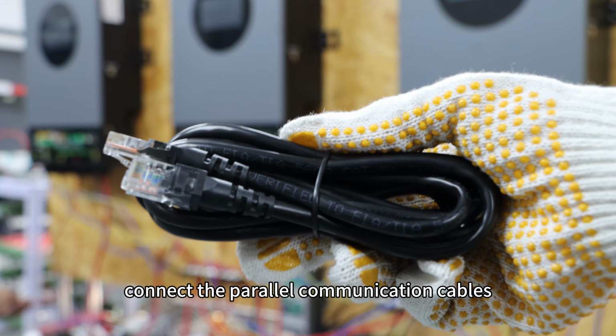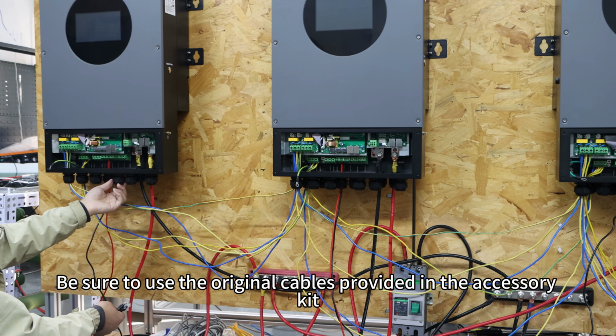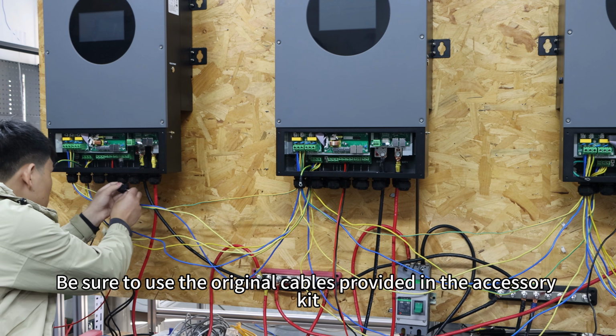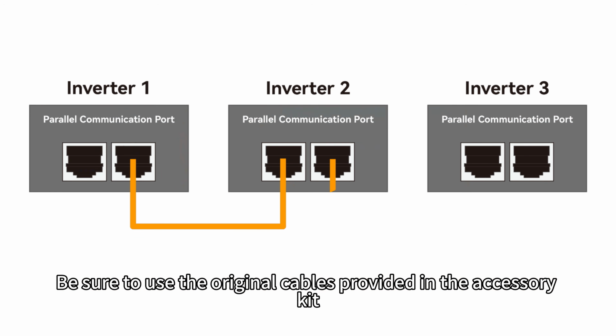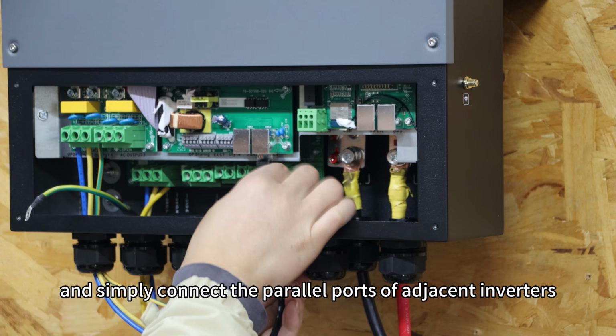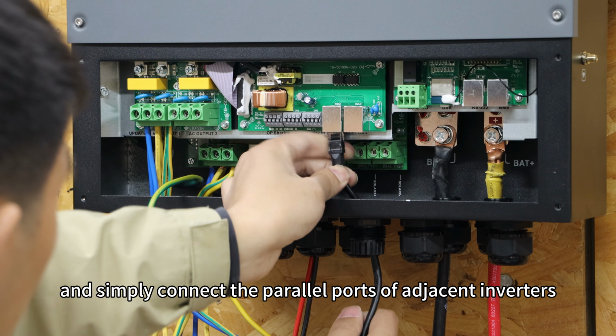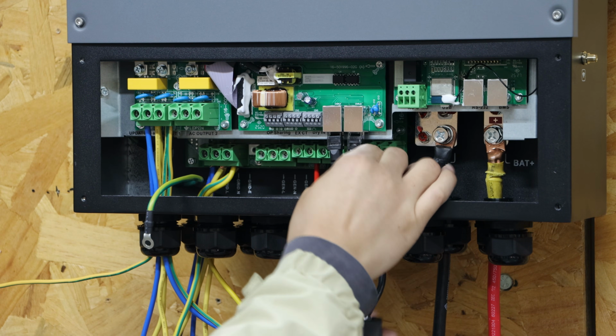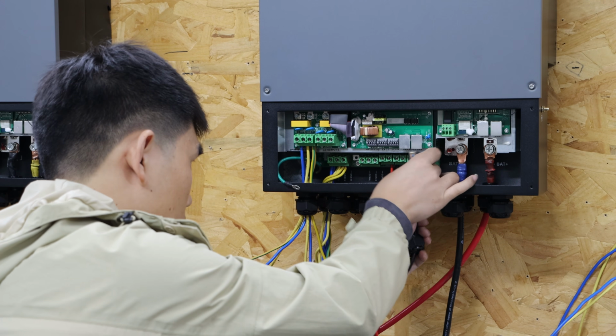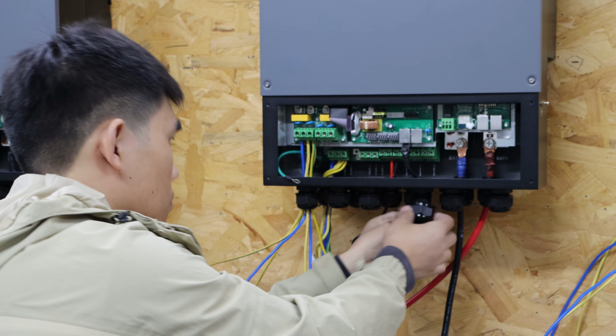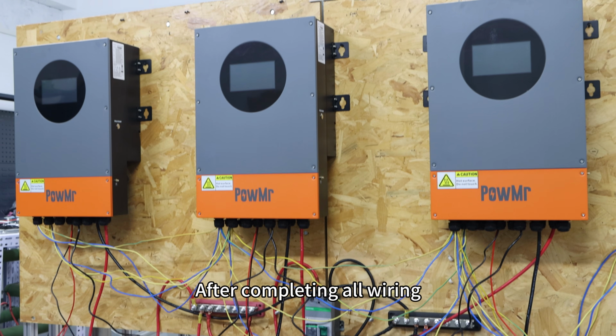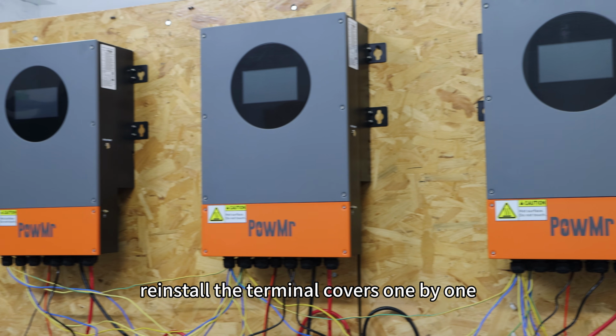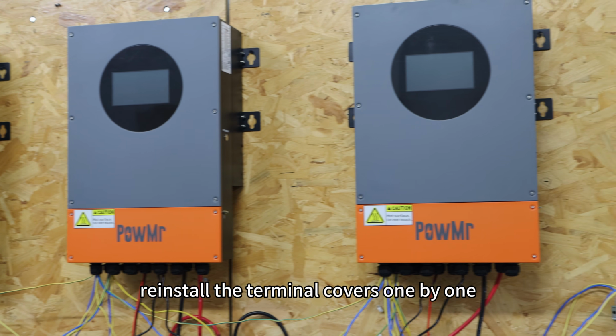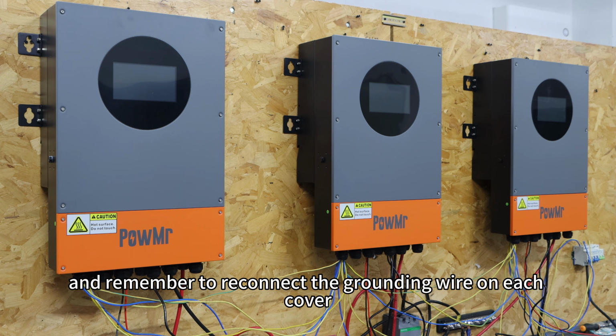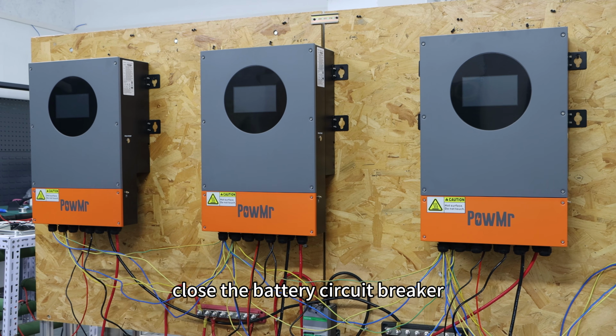Finally, connect the parallel communication cables. Be sure to use the original cables provided in the accessory kit and simply connect the parallel ports of adjacent inverters. After completing all wiring, reinstall the terminal covers one by one, and remember to reconnect the grounding wire on each cover. Then close the battery circuit breaker.